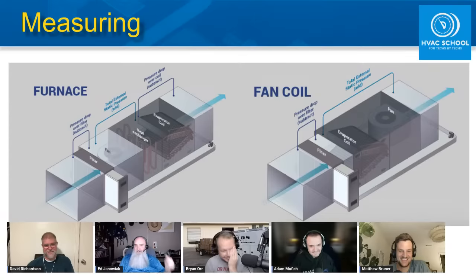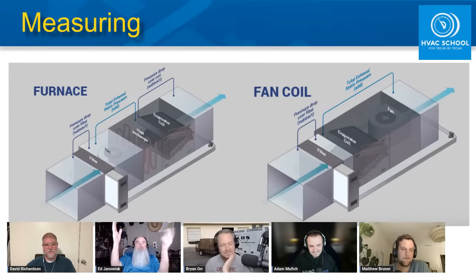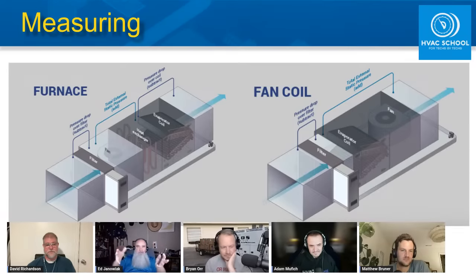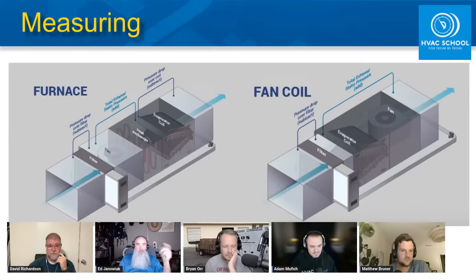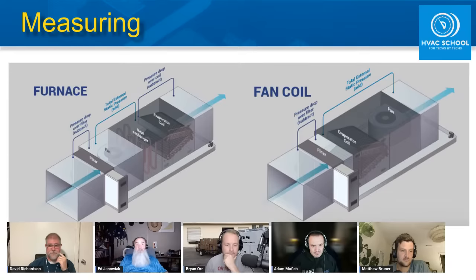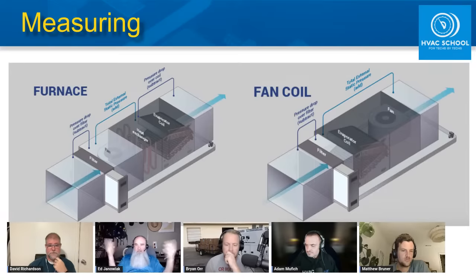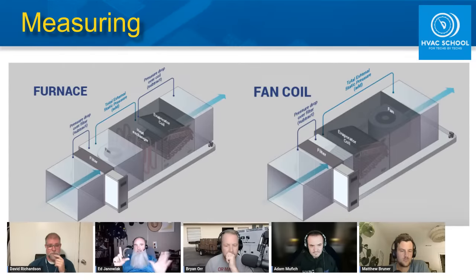On the friction rate worksheet, for a furnace with a maximum external static pressure of 0.5 inches WC, you can allocate component budgets: 20% for return duct, 20% for supply duct, 20% for the filter, and 40% for the coil — roughly 0.10 for duct pressures, 0.10 for filter pressure drop, and 0.20 for coil pressure drop. Instead of those numbers being abstract values, now you have something to point to. The farther those numbers go from their budgets, the more they should draw your attention to that component.